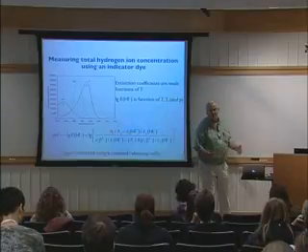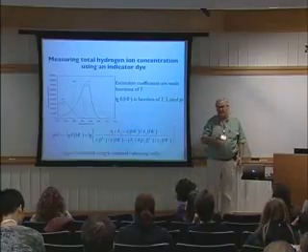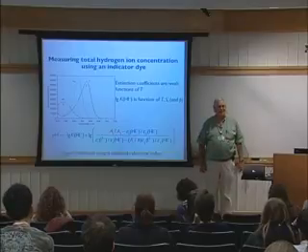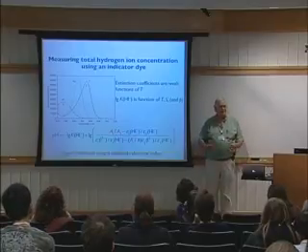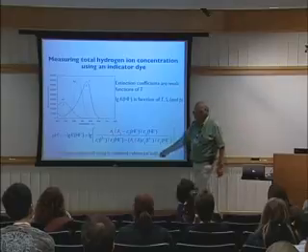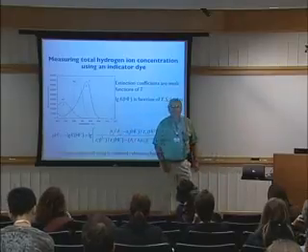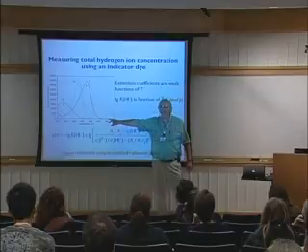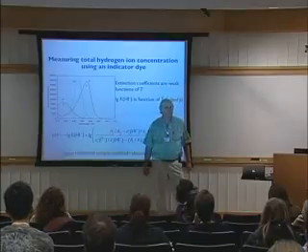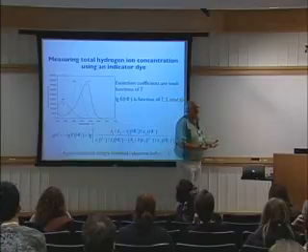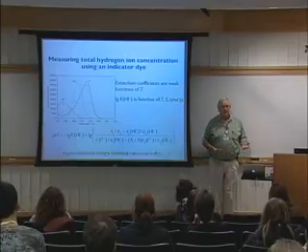There are other corrections because you took the cell out and you put it back and things aren't perfectly lined up. So we actually make a measurement at a third wavelength out here, which should be the same and should be almost nothing between your two measurements, because it's not dependent upon the indicator being there.